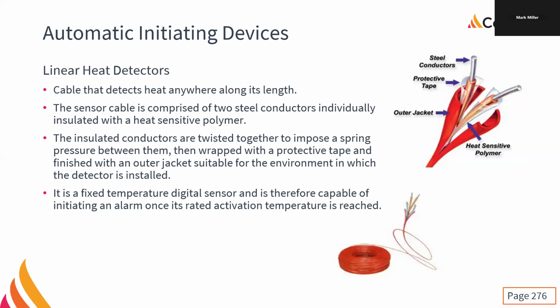So they are odd. It's a very, very fancy cable. The stuff is not cheap and is not easy to work with. It is steel conductors, not aluminum, not copper. They actually use steel because they want it to be very, very rigid, because we twist them together to impose a spring pressure between them, and then wrap them with protective tape and put on an outer jacket that is suitable for the environment, to keep it all protected.